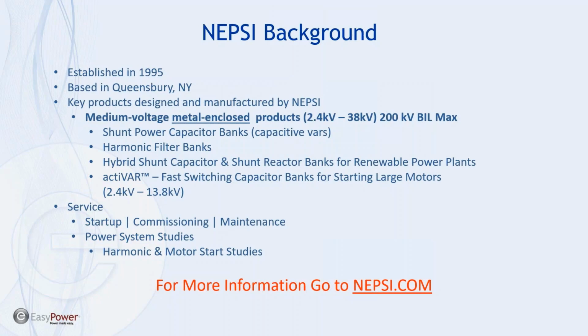In addition to manufacturing metal enclosed systems, Northeast Power Systems also offers services in startup and commissioning, as well as maintenance. We do power system studies, but only studies to provide support for the products we sell. So primarily medium voltage metal enclosed systems, harmonic filter banks, they require harmonic studies and motor start studies. Motor start studies are performed to support the actiVAR solution. It's a relatively new product, about 5 years old, which involves fast switching capacitor banks for starting large motors. This is an alternate solution to starting large motors.